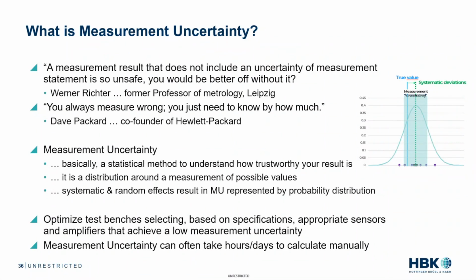Basically, you want to base your selection of equipment and sensors on the specifications. Some data sheets don't have all the information, so sometimes you may need to dig a little bit deeper to research and find out what those specifications are. But you want to use appropriate sensors and amplifiers that achieve a low measurement uncertainty so that you can have a more trustworthy measurement. Unfortunately, measurement uncertainty can often take hours and even days to calculate manually.